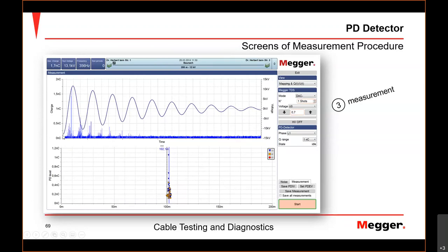Then this switch closed, and we got the resonant voltage here attenuating and dying away. So our first period, actually, we will later look at only our first period because that's the voltage we've set. What are these partial discharges doing? And while we apply the voltage, we will see discharges. And here we see, for example, the highest pulse. Let's look at the highest pulse. Actually, this is not one pulse, but two corresponding pulses. One that came straight into the instrument to be measured, and one that went in the cable to the far end, was reflected and came back.